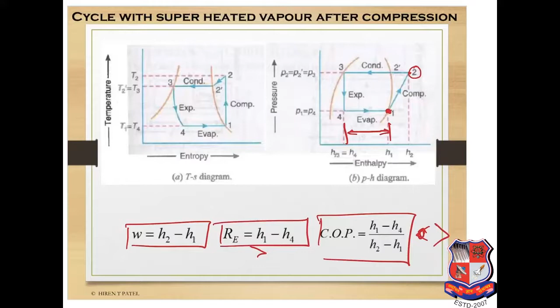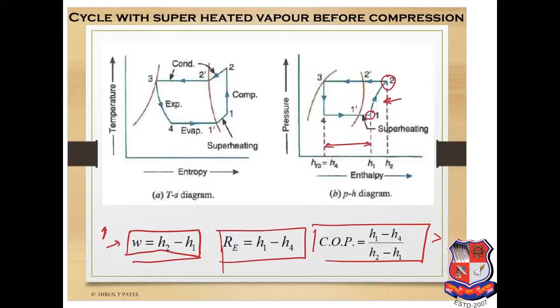Next modification is cycle with superheated vapor before compression. So here the vapor which is entering into the compressor is superheated before entering, and after compression it is also superheated. So here also the refrigerating effect is far greater, but the problem is that the work done H2 minus H1, that is given to the compressor, is required higher compared to other modifications or other cycles. So compared to refrigerating effect and work done, the COP is higher than the previous cases, but the drawback is only that we have to give more work to the compressor, as it has to handle more volume of the vapor, as vapor is superheated.